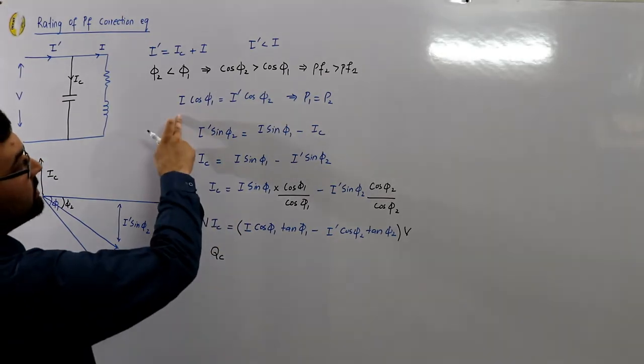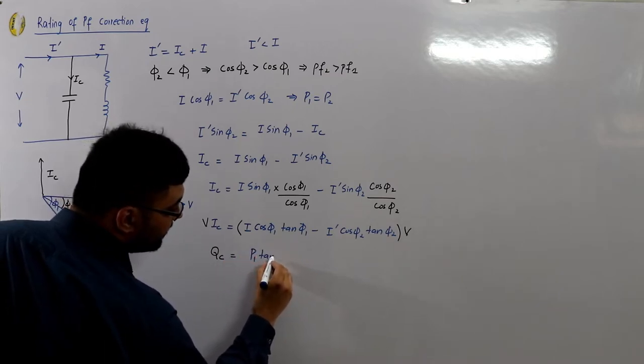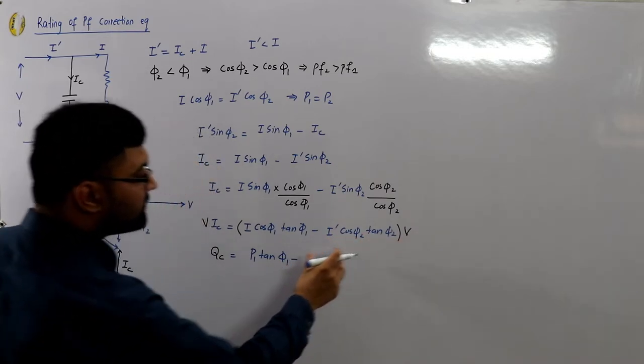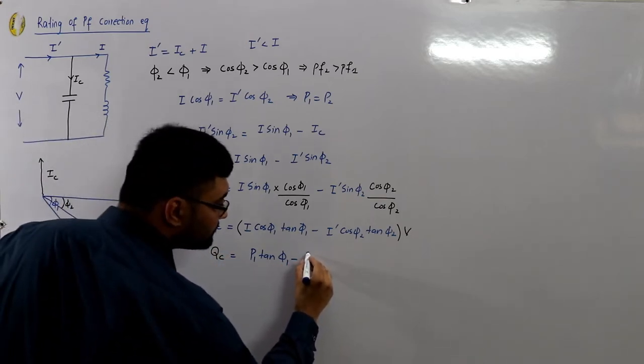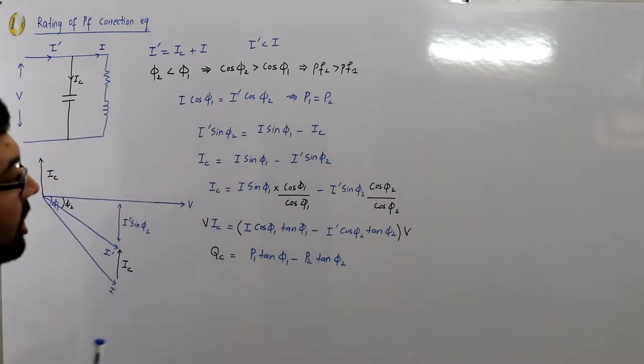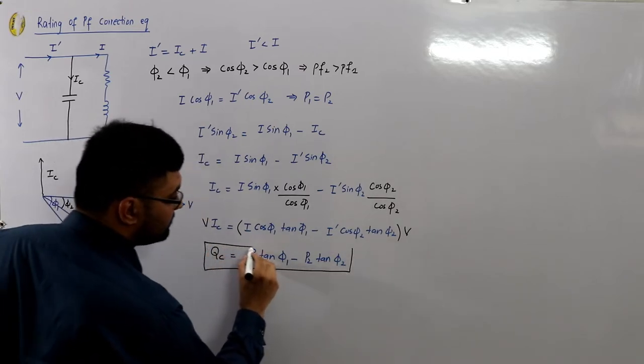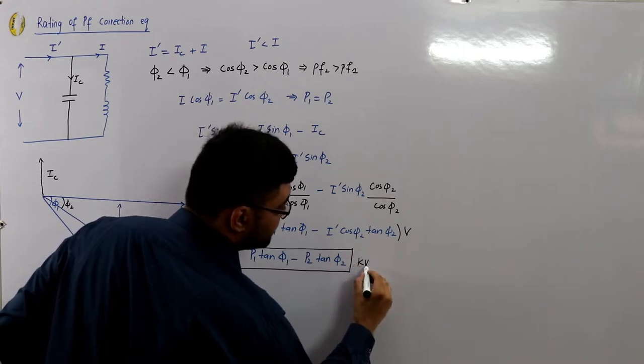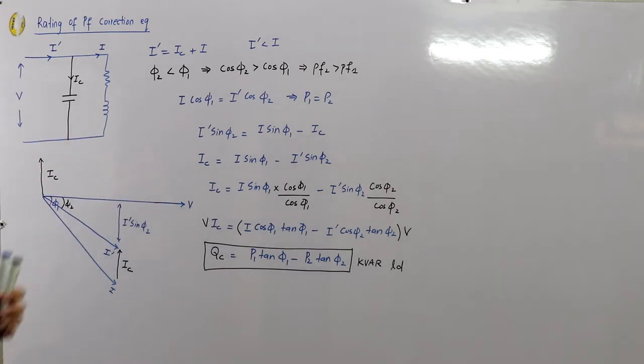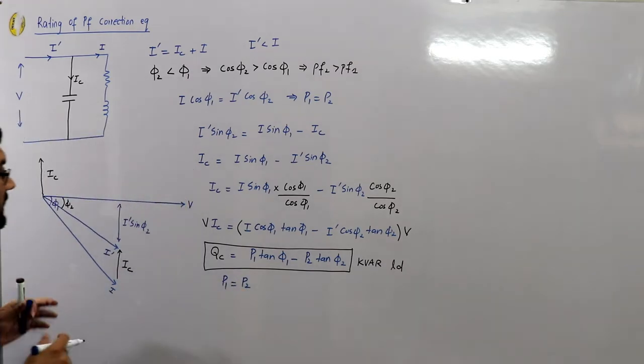So we get: QC = V·I·cosφ1 · tanφ1 minus V·I'·cosφ2 · tanφ2, which equals P1·tanφ1 minus P2·tanφ2. These are the KVARs required — the leading KVARs you inject into the system to achieve the desired power factor.